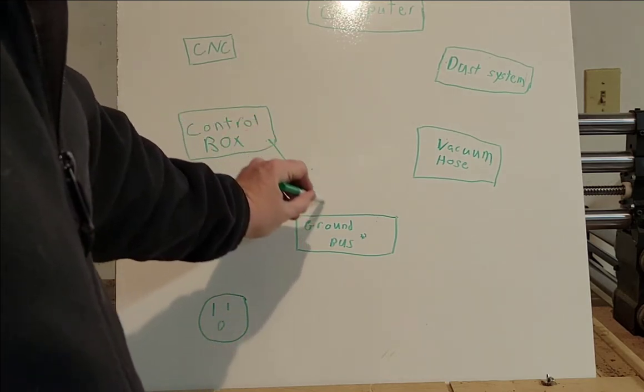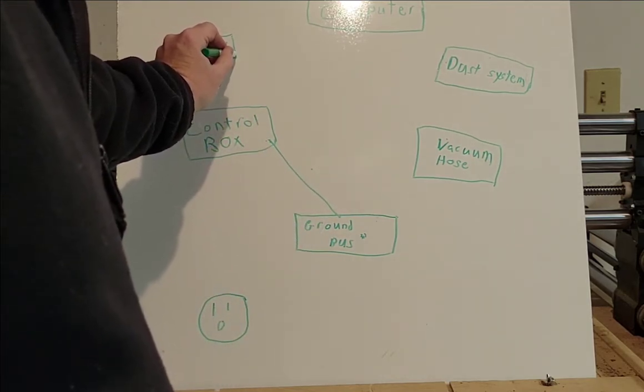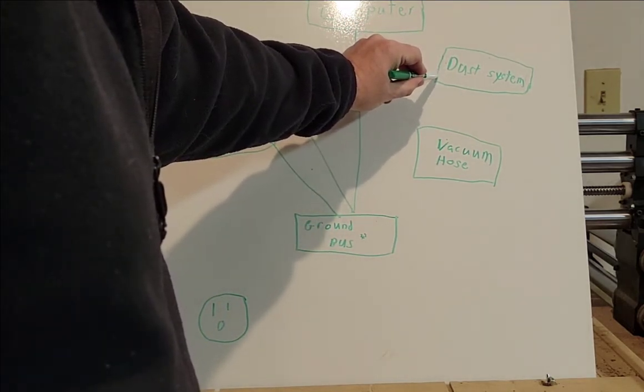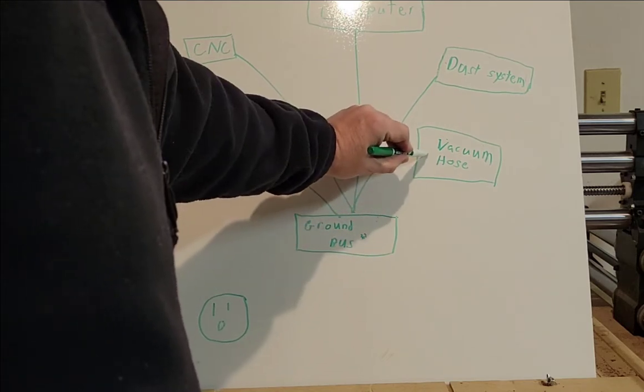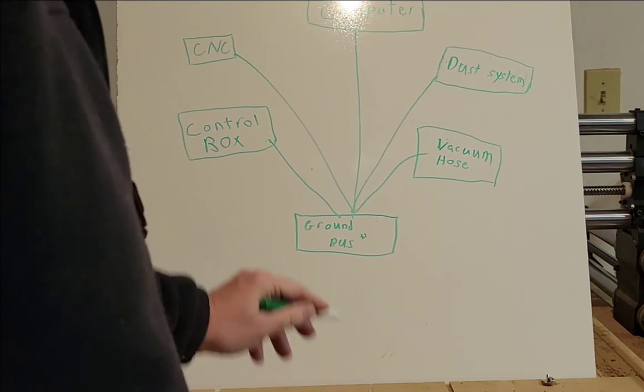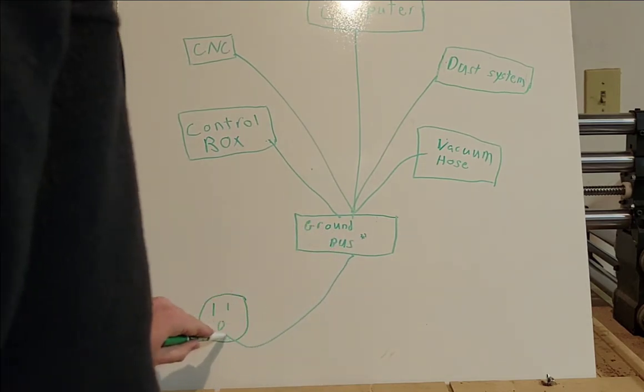And essentially this is what you do: you take the ground from your control box, it comes here. You take the ground from your CNC, it comes here. You take the ground from your computer, it comes here. You take the ground from your dust system, it comes here. You take the ground from your vacuum hose which is a wrap, goes to there. The ground bus goes right there.